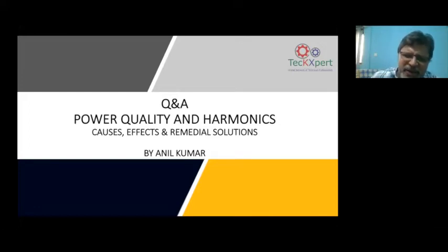And coming back to the capacitor bank failures, I'm sure there is some harmonic amplification happening, as I said before, parallel resonance problems. That could be the reason for the capacitor failures. So the quick answer is yes: go in for LEDs with EMI filtering and capacitor banks correctly designed so that harmonics do not get amplified. Your reactor is a temporary solution because it opposes the rate of change of high frequency currents coming from the LED. So it is saving the system for now.